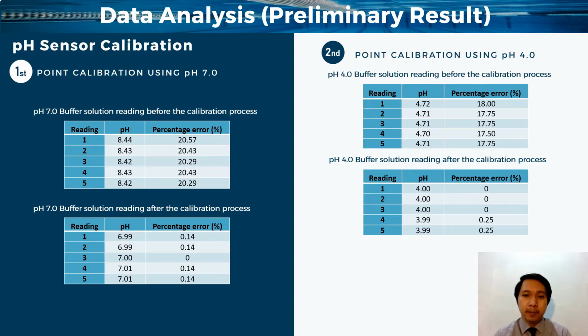As you can see here, the pH sensor has undergone a 2-point calibration procedure. This is to ensure better accuracy and also a broader range of accuracy compared to only 1-point calibration. So the blue side is the first point calibration using pH 7 result. The buffer solution reading has significantly dropped from 20% to only 0.14% of percentage error. And the white side is the second point calibration using pH 4, and the percentage error has dropped from up to 18% to only 0.25%.